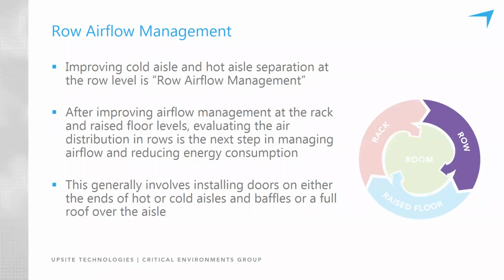So when we talk about row airflow management, we're referring to improvements in separating cold supply air from hot exhaust air at the row or aisle level. Row level improvements are typically addressed after you've taken care of the rack level and floor level improvements. And row level improvements usually always involve sealing off the hot or cold aisle ends with some type of door and dealing with the area above the row or aisle by capping the cold aisle or channeling the hot air above and out of the hot aisle.